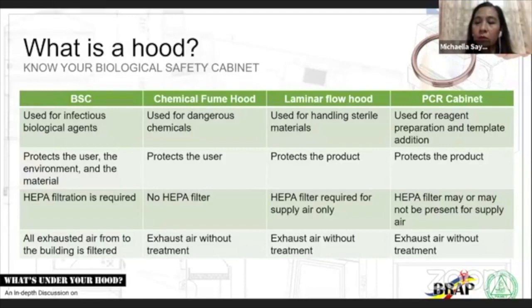Now, the chemical fume hood, on the other hand, is just used for dangerous chemicals. It's meant to keep the fumes away from the user. It protects the user. There's no requirement for HEPA filtration. Although there are chemical fume hoods that have neutralizers, they have carbon filters, just to mitigate a certain percentage of the chemicals. And exhausted air is not treated. Again, there are add-on systems to your chemical fume hood that could help mitigate the vapors of your chemicals.